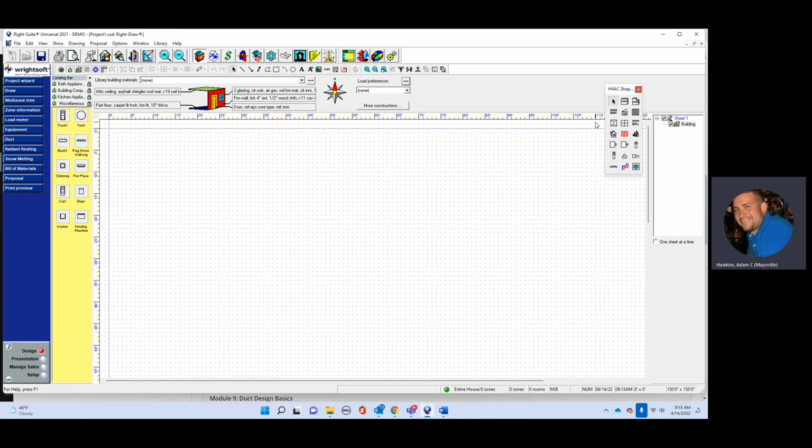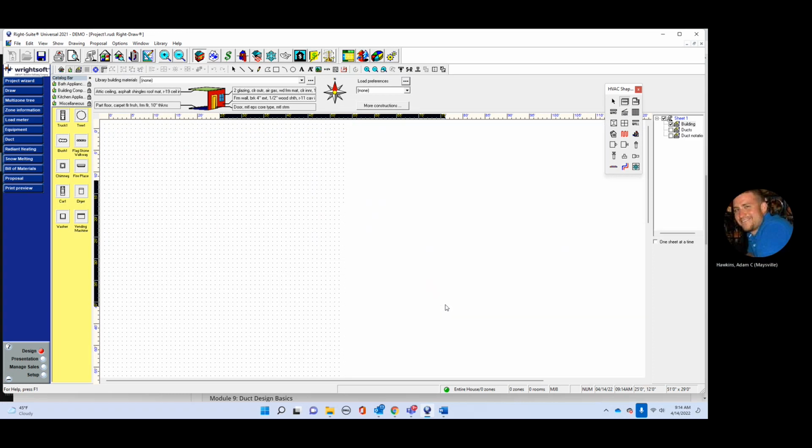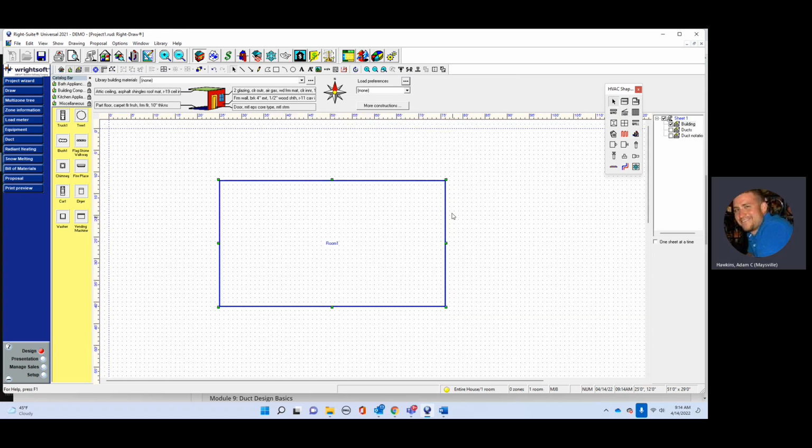All right, now we're going to start drawing. The way you're going to do this, you're not going to draw it like you think you would. If you're doing a block, you can do that. Just real quick, I'll show you. The house itself is 51 by 29, 1,479 square feet. I'll go over here to room and draw that house really quick, 51 by 29, and throw that on here. And I've got a house. Then I can start throwing windows and doors in that and make a block. If I was doing a block load, that's the way I would do it.